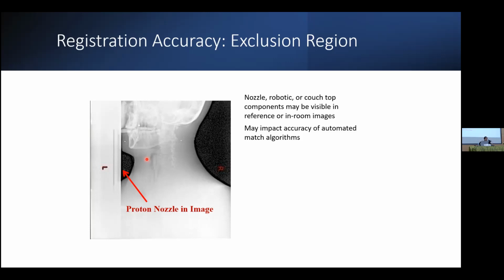That's part of the things you write during your acceptance test and your acceptance test procedures, and have the conversation with the vendor. Because the worst thing is you get all these things, you test everything nice at isocenter, but then you're doing a breast treatment that you're slightly off and you had to shift, and now you can't see anything because the imagers are being obstructed.